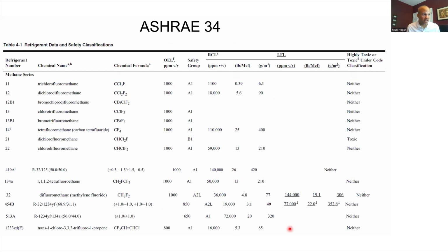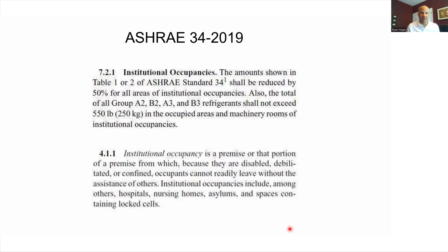The first thing to understand is that there are two numbers there. Even though it only says one thing, it's actually two. There's the regular refrigerant concentration limit for regular buildings, and then there's the institutional occupancy limit. An institutional occupancy, for lack of better description, is a space of a building, or even the entire building, where people are not capable of removing themselves from the building in an emergency. So, for example, an ICU at a hospital: if there's a problem in the building and they have to evacuate, you're probably not going to get out of the bed and walk out yourself. Someone has to take you out, right?